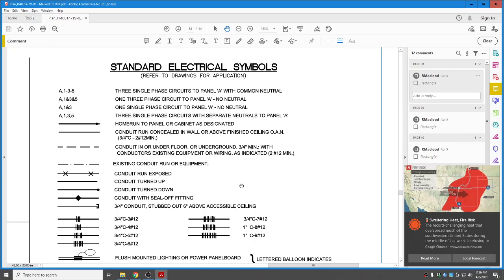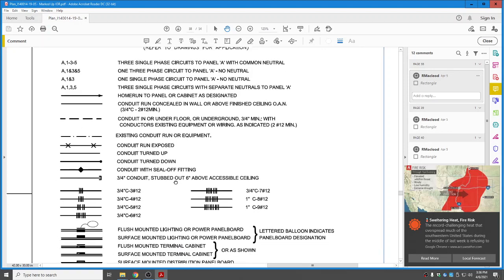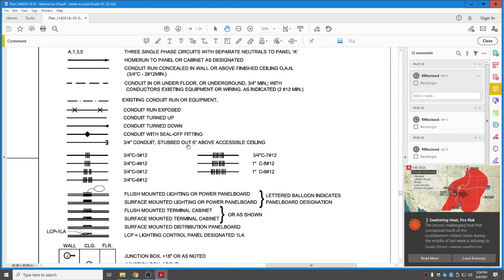Existing conduit run or equipment. Conduit run exposed, a conduit turned up, conduit turned down, conduit with seal-off fitting, 3/4 inch conduit stubbed out, 6 inches above an accessible ceiling. This is where it gets a little more interesting. You'll use this quite a bit more. 3 hash lines denotes a 3/4 inch conduit with 3 number 12 wires. 4 lines, 3/4 conduit with 4 number 12s. And you can just read your way through these as the conduits get larger and the wire sizes get larger.